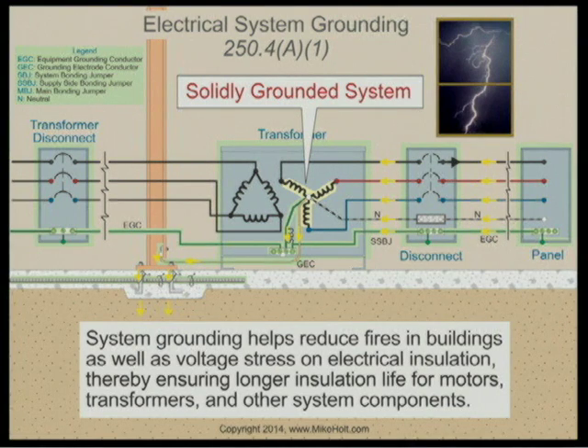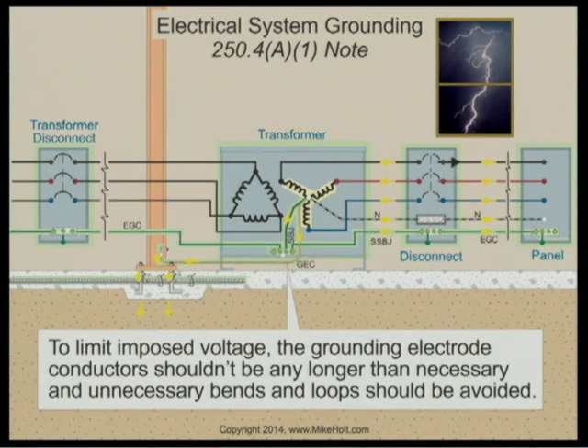Eric, were you going to say something? Yeah, I just want to point out, because this is such a good graphic right here, it shows it very clearly, that in a separately derived system, you have your choice to bond either the transformer or the first disconnect. This particular graphic shows where the transformer is bonded to the case, but we could just as easily have bonded the first disconnect. Right. Exactly right. All right. Let's go to this graphic here.